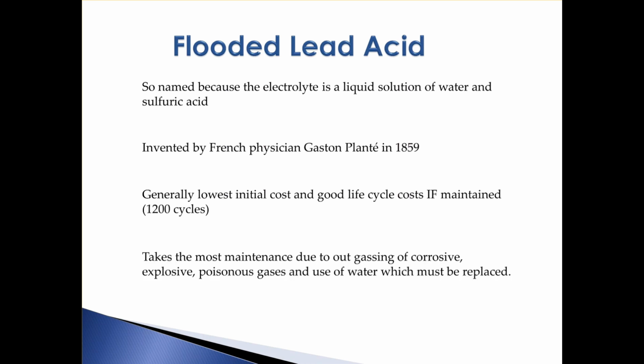But they also take the most maintenance. They are subject to outgassing, and that's due to the charging process and the discharge process, and that outgassing will consist of water, sulfuric acid, and in some cases hydrogen. So this gas is corrosive, it's explosive, and it's poisonous. Other than that, you don't have to worry about it. And you also are going to use water, which must be replaced on a regular basis. Failure to replace the water is the easiest way to kill a flooded lead-acid battery.